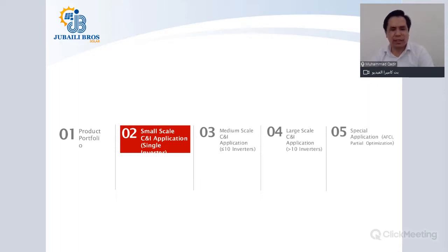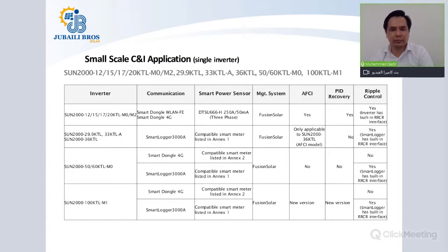Coming to small scale C&I application with a single inverter scenario. This is a summary, and a single inverter can be 12, 15, 17, 20, 36 kilowatt size, 50, 60, or 100 kilowatt. Coming to the first column, the inverter, there can be different scenarios. Scenario 1, you can use 12, 15, 17, or 20 kilowatt, either the existing version M0 or the newer version M2. The second scenario is the 36 kTL, the third scenario 50 and 60, and the fourth scenario is the 100 kTL.